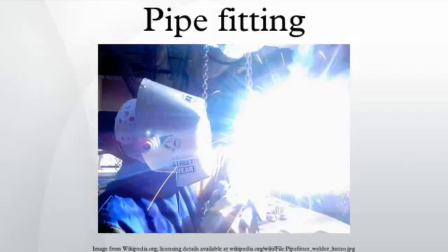Steel pipe is sometimes joined using threaded connections, where tapered threads are cut into the end of the tubing segment. Sealant is applied in the form of thread sealing compound or thread seal tape, and it is then threaded into a corresponding threaded fitting using two pipe wrenches.